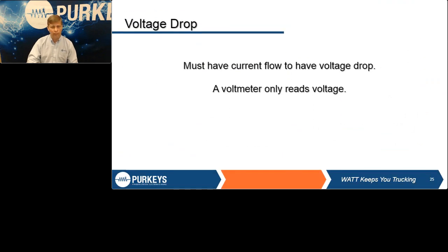So, a summary of our voltmeter and voltage drop: the voltmeter only tells us the difference between 2 different points. In order to have voltage drop, we have to have a load, and we have to know what that load is to properly test it.